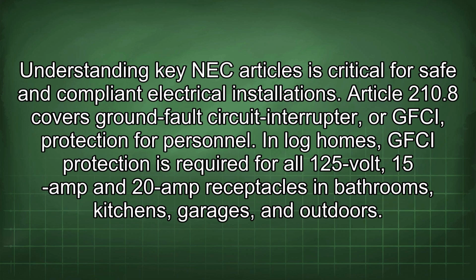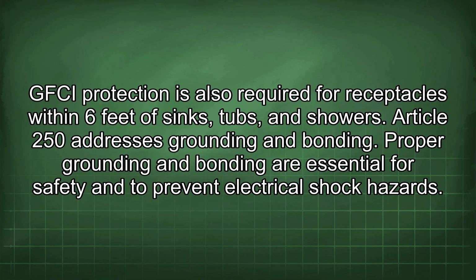Understanding key NEC articles is critical for safe and compliant electrical installations. Article 210.8 covers ground fault circuit interrupter, or GFCI, protection for personnel. In log homes, GFCI protection is required for all 125 volt, 15 amp and 20 amp receptacles in bathrooms, kitchens, garages, and outdoors. GFCI protection is also required for receptacles within 6 feet of sinks, tubs, and showers.